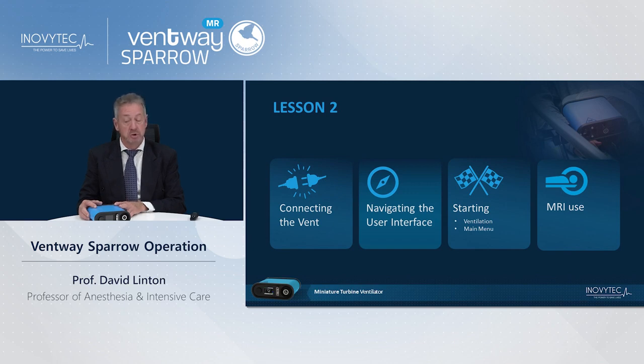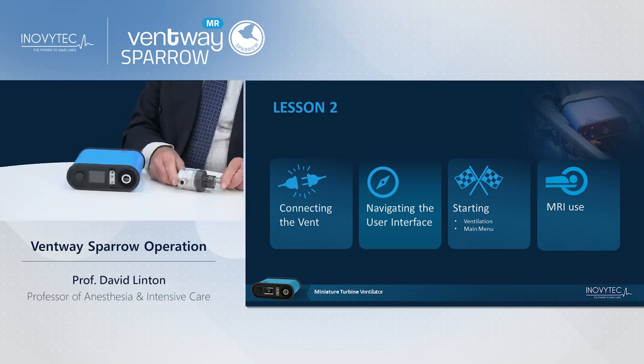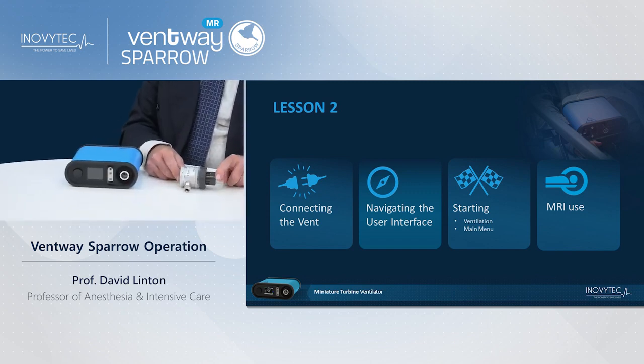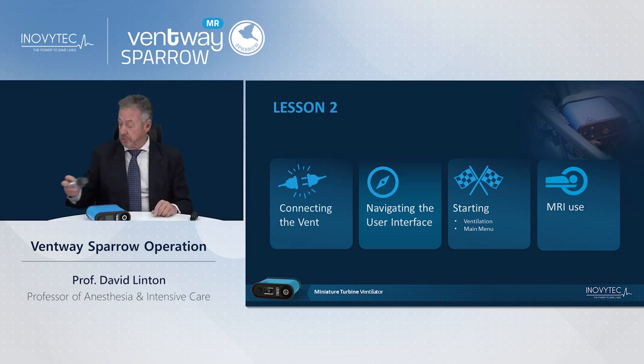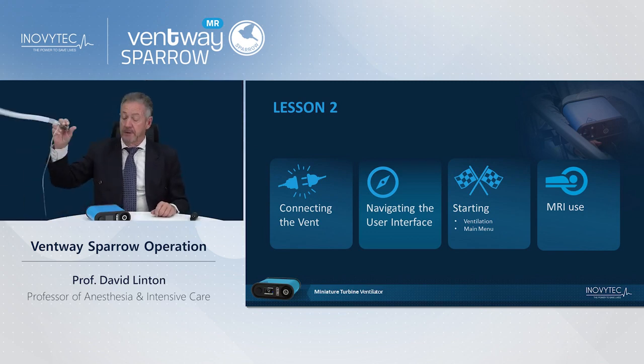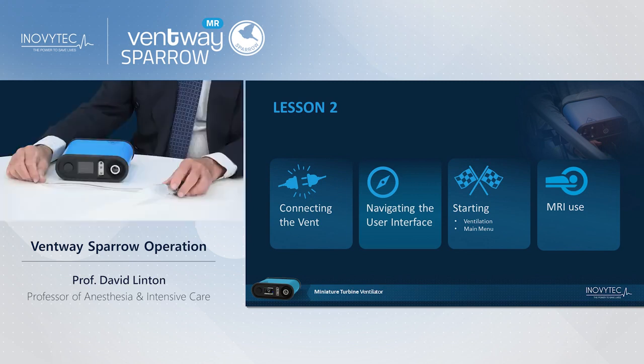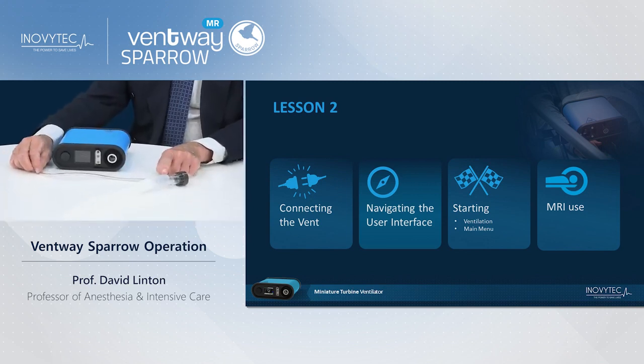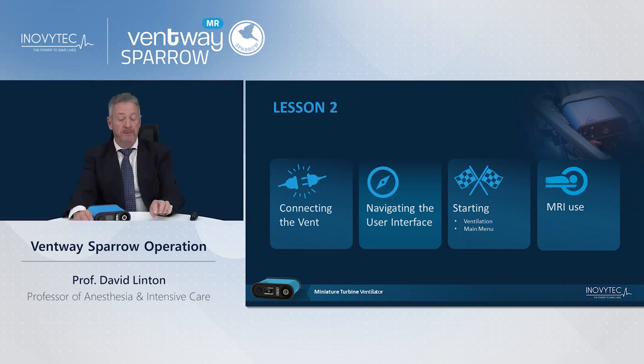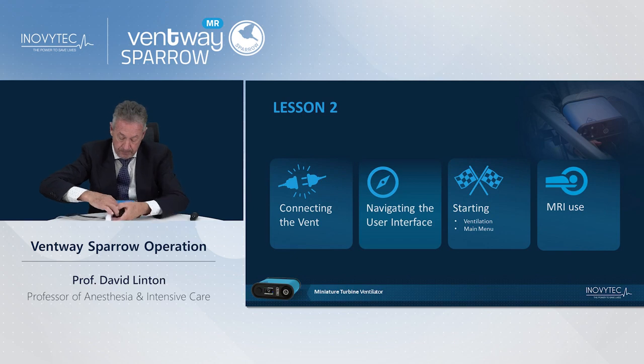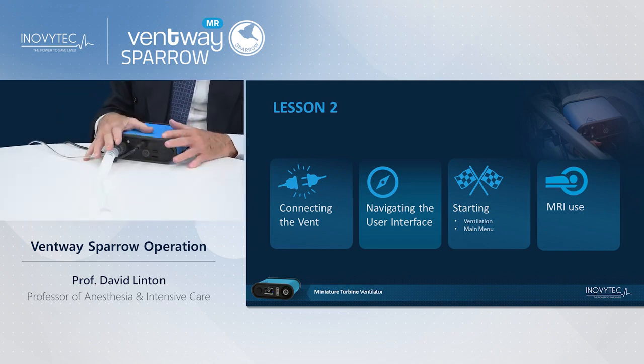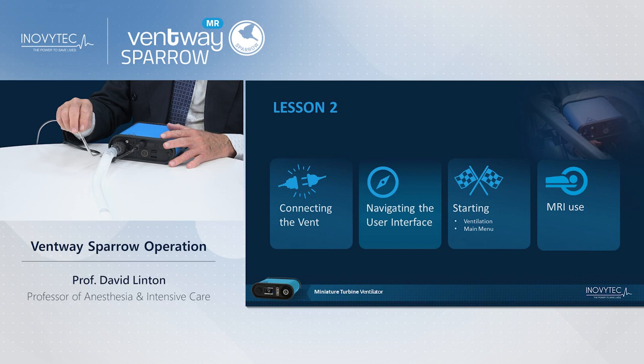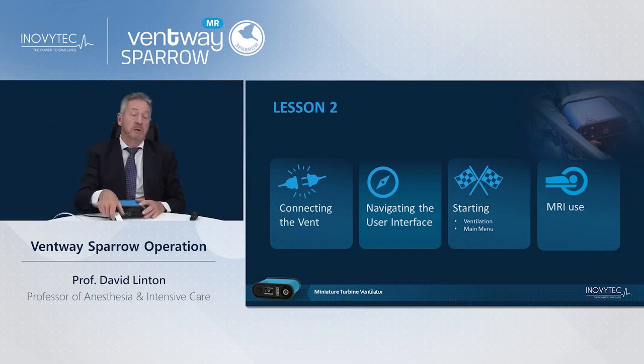You need only an oxygen supply source, which can come either from a valve connected to a pressure source by a DISS cable, where you can control the oxygen concentration, or you can add this very cleverly designed oxygen concentrating device, which allows oxygen to flow into it and then collects the oxygen. When it goes into the oxygen input at the back, you can provide 1 or 2 liters a minute to give you 30-40% oxygen, according to the minute ventilation the patient is getting.